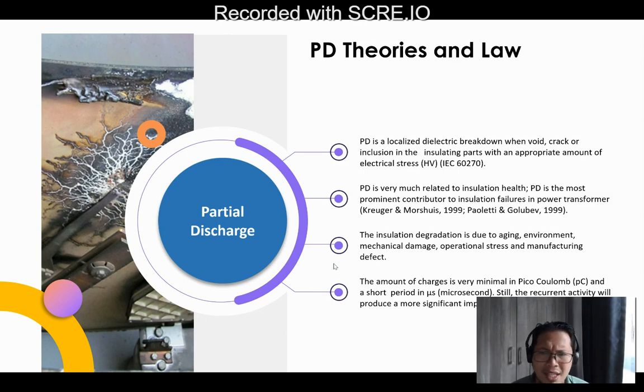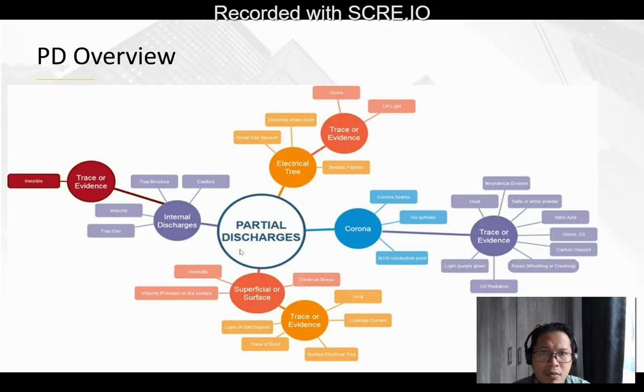Even though PD happens at very minimal magnitude, in picocoulombs, and for a short period, in microseconds, the recurrent activity will produce a more significant impact on the insulation of the transformer. Based on the PD overview, there are four main types of PD: internal, electrical, corona and superficial. The difference between these four is in the evidence. If we say corona, it's not coronavirus, it's PD corona. It leaves heat, salts, powder, nitric acid and ozone deposits in our equipment. Whereas my research focus, internal discharge, is invisible because it happens inside the transformer main tank.